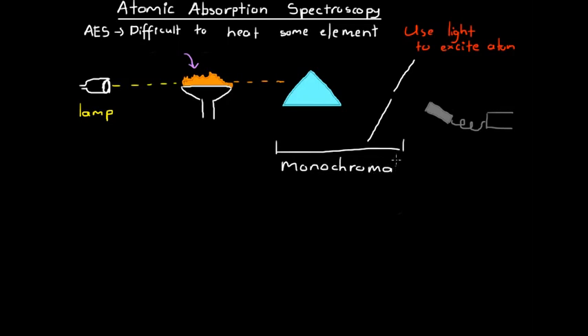A monochromator takes advantage of the fact that different frequencies of light diffract by different amounts as they pass through a prism. The prism separates colors such as red and blue light, and then a movable slit selects only a specific color to measure. For example, with the slit positioned for purple light, we can measure how much purple light is getting through. By moving the slit, we can measure how much of each frequency of light passes through the atomic vapor.